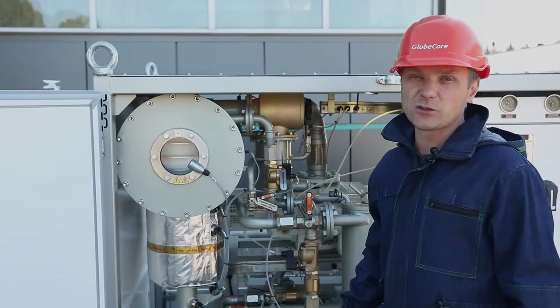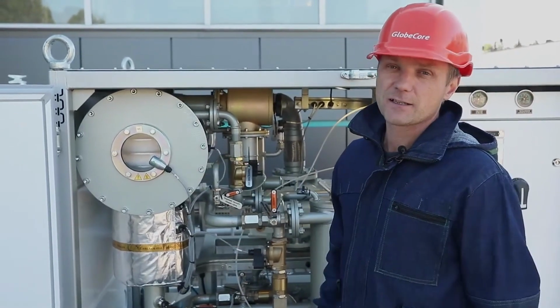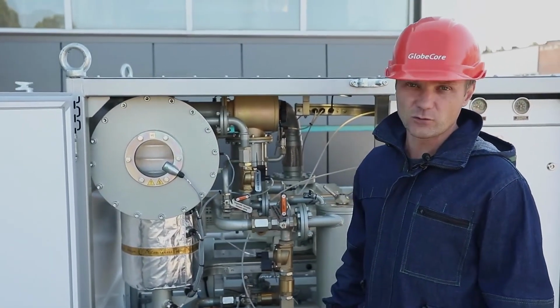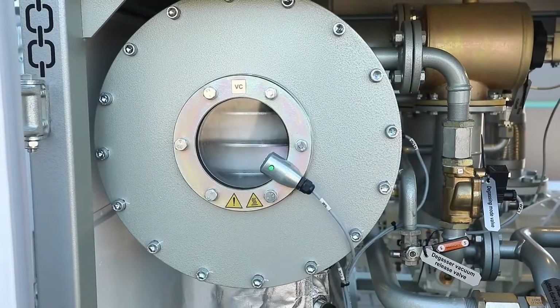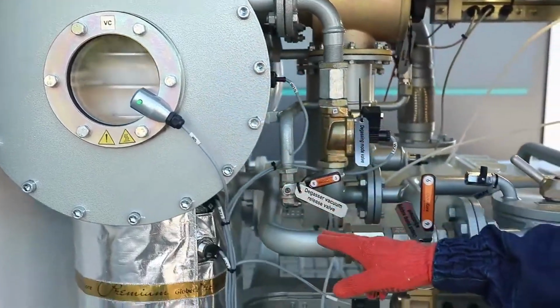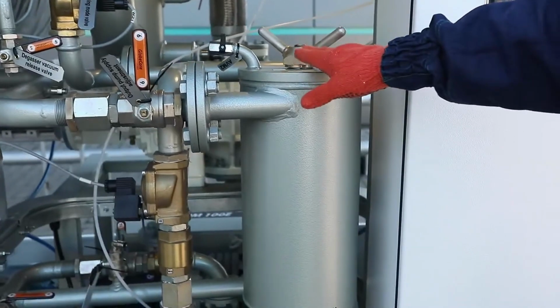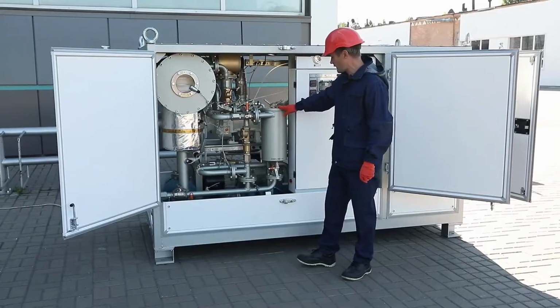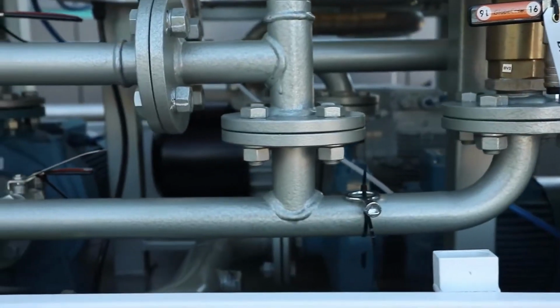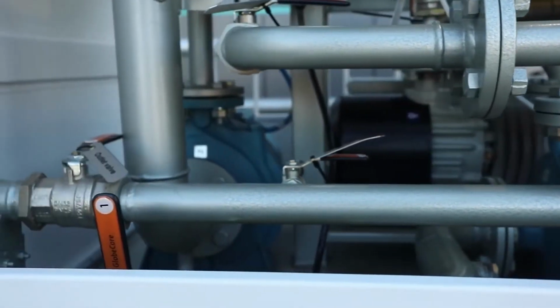After the vacuum chamber, the oil is additionally filtered while going through another fine filter with a filtration fineness of 1 micron and then flows to the outlet. The presence of 3-stage filtration in the unit ensures a high efficiency of mechanical impurities removal from oil and extends the operation life of filter elements.